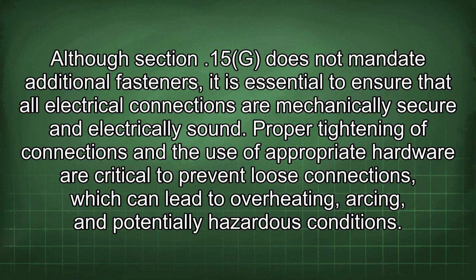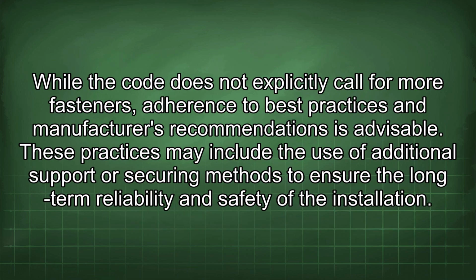secure and electrically sound. Proper tightening of connections and the use of appropriate hardware are critical to prevent loose connections, which can lead to overheating, arcing, and potentially hazardous conditions. While the code does not explicitly call for more fasteners, adherence to best practices and manufacturers' recommendations is advisable.